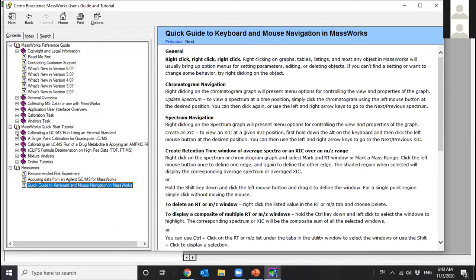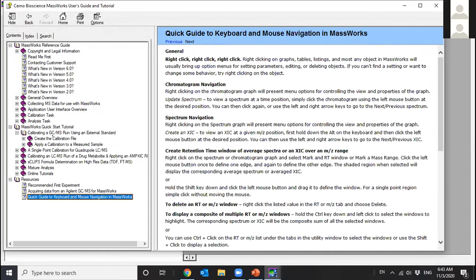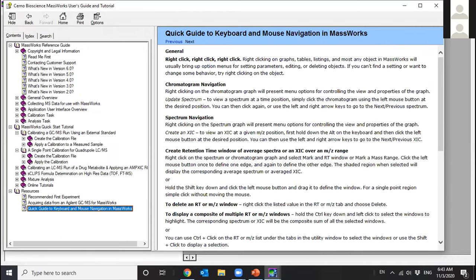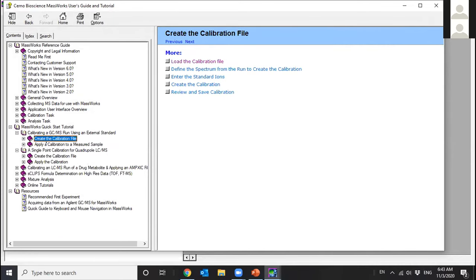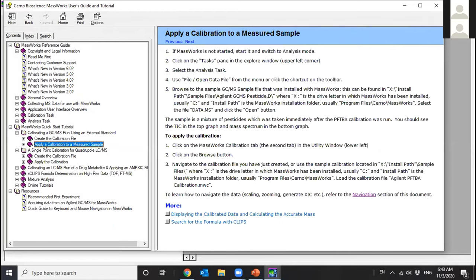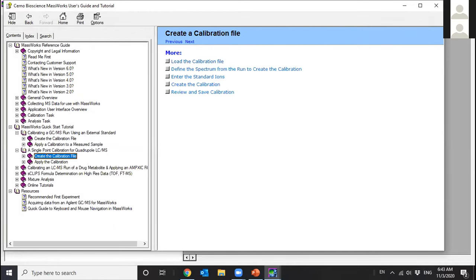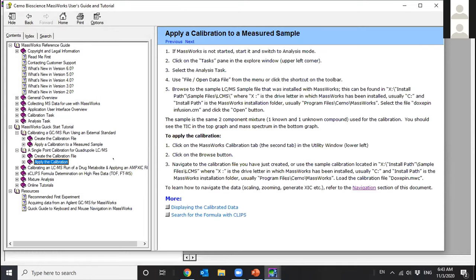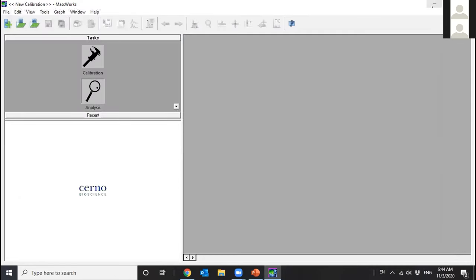Goes through the first two sections, how to calibrate using a GCMS run and how to calibrate using an LCMS run. So for GCMS here, create the calibration, apply the calibration for analysis, and for the LCMS, how to create the calibration and apply the calibration to the analysis. Using all pre-installed data that's available to you to go through the process. So that's the electronic help that's available to you at your fingertips at all times. And of course you can reach out to us to ask for any help as well.